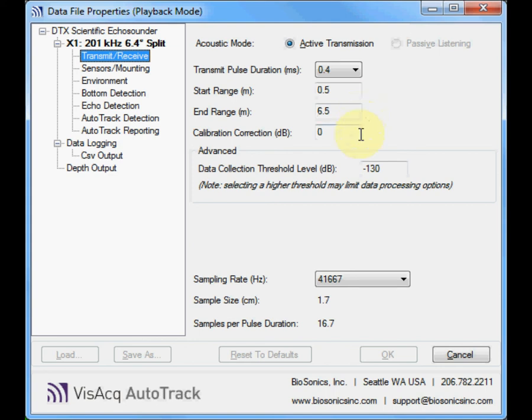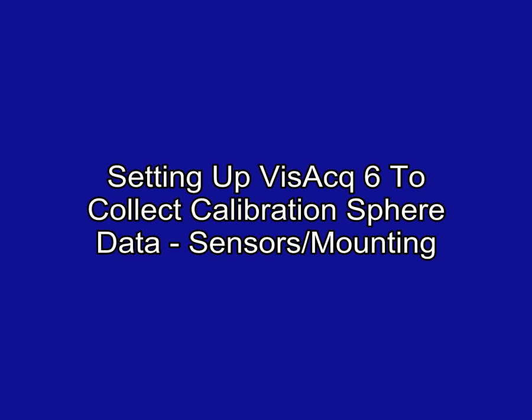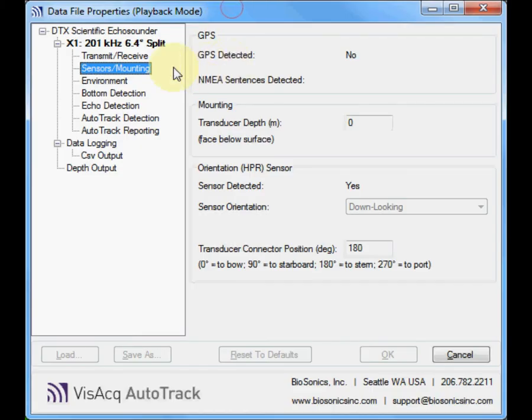Calibration correction, this would be the offset where you enter it, and you would calculate this in the next step when we analyze our calibration sphere acoustic data. And data collection threshold, we recommend using the full threshold minus 130 in most cases. Next is the sensors and mounting tab. The only thing you'll be entering in here is the depth of the face of the transducer below the surface in this box.